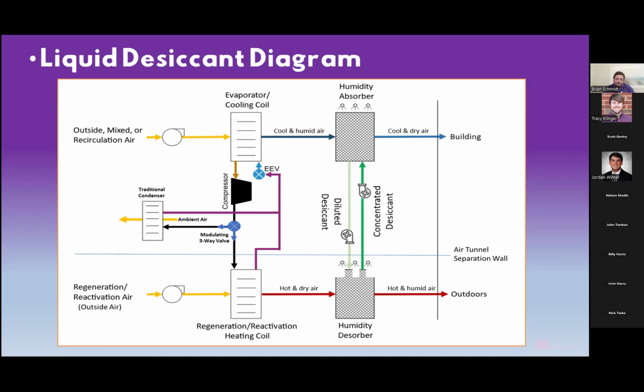What I also want to note on this is what the liquid desiccant system is. So it's really at its core, it's 2 pads, 2 pumps, and some sensors. So as you see here, we have our absorber, we have our desorber. We do have 2 fractional horsepower pumps. These are off-the-shelf pumps. You can't get them at Home Depot because obviously liquid desiccant is a very corrosive material, so it needs to have a certain type of pump. But these are not proprietary to Mojave. You can certainly order these online or wherever you'd like to. And so we do have, again, 2 pads, 2 pumps, and then some sensors. We have very, very sensitive leak detection systems. And underneath the entire liquid desiccant system is a plastic tray.